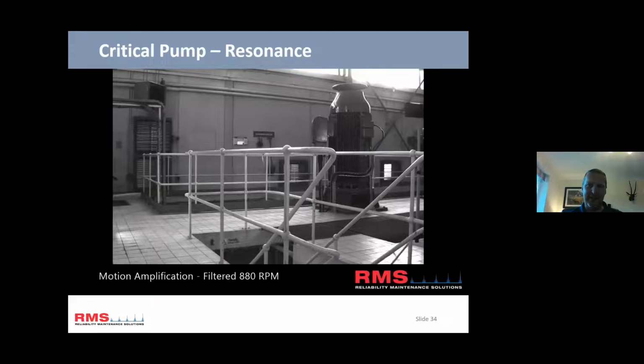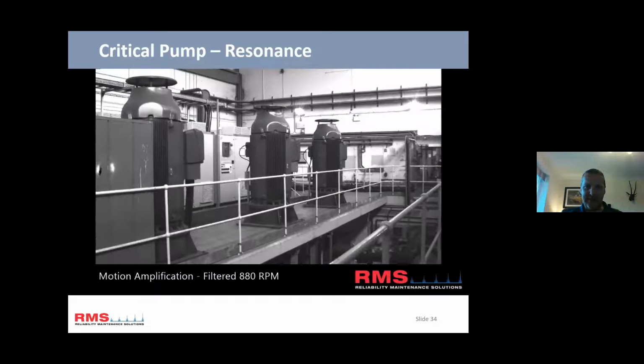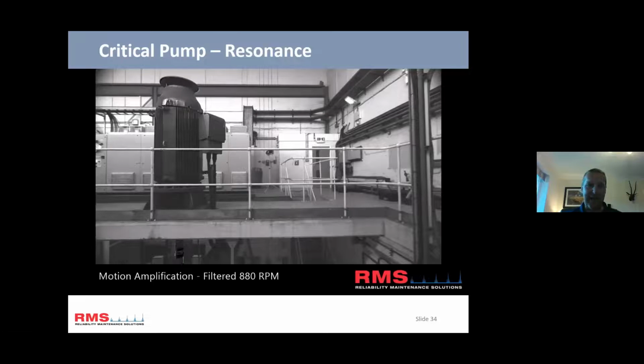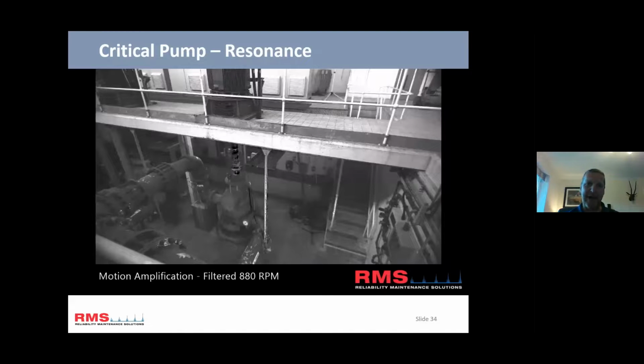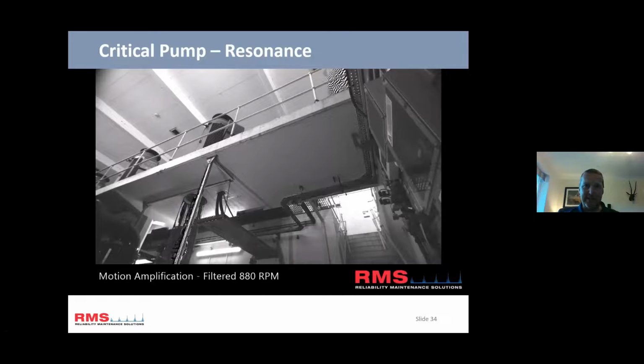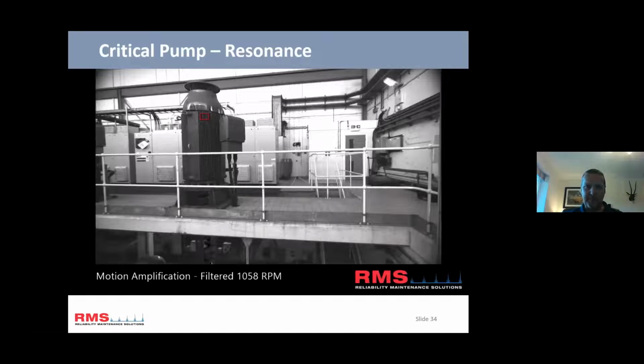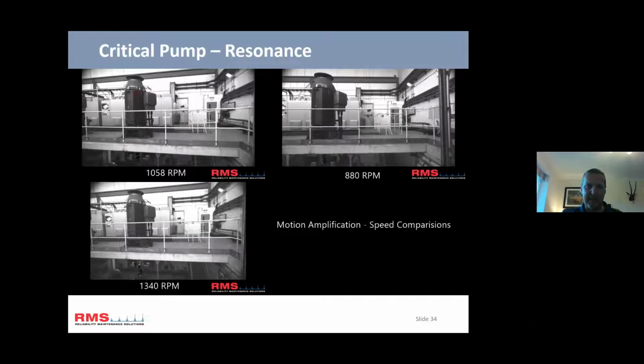We actually set the machine at the point where the vibration was highest and then filmed it. So you can really see that floor moving. Now, the other pumps actually had supports underneath, but for some reason, I don't know why, they hadn't added them to this area. The customer knew that, but when they saw the video, it was just so obvious what the problem was. So yeah, classic resonance excitation. When the speed went up, the vibration disappeared. See, it reduces there when the speed's a bit higher. Different speeds we did it at.